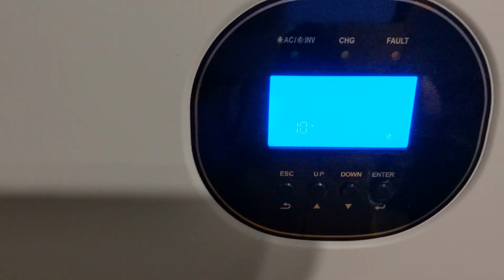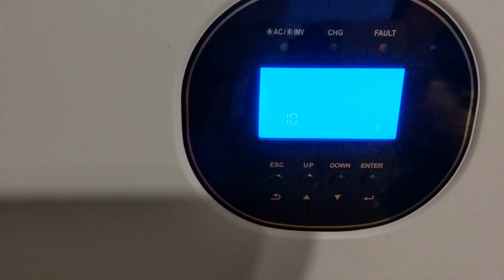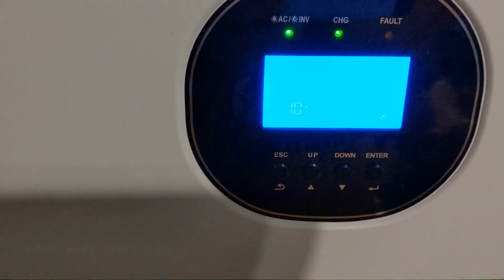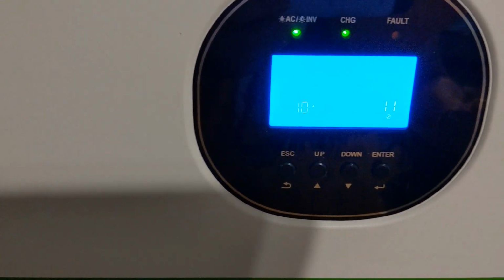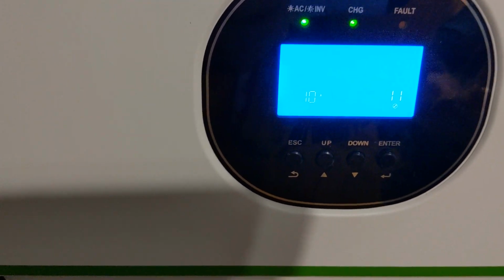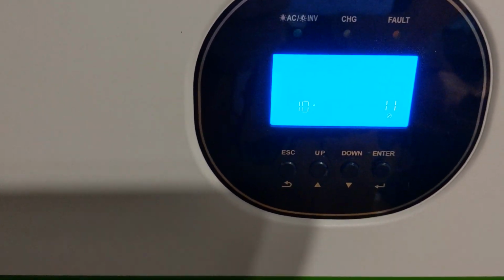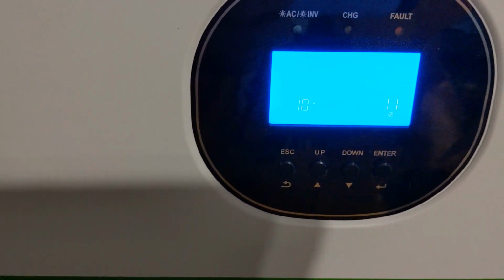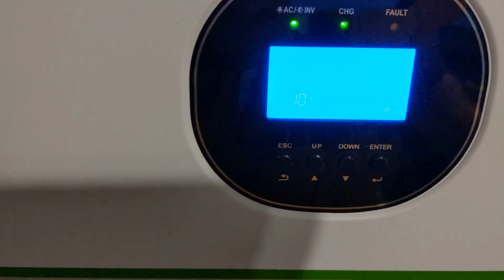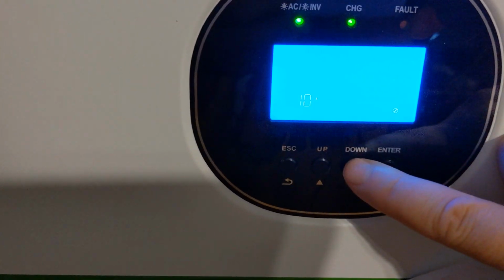So now we're down to the maximum utility charging current. Again, you can set this up to a maximum of 30 amps, so it'll pull 30 amps per inverter from the grid. So a maximum of 60 amps max, 30 per. I have this set to 10, so that would be a maximum of 20 amps for the two of them combined to top off my batteries if I ever need to use this mode.